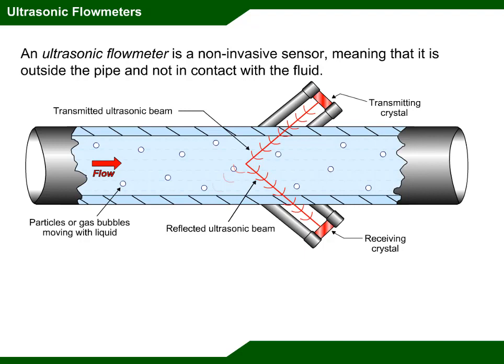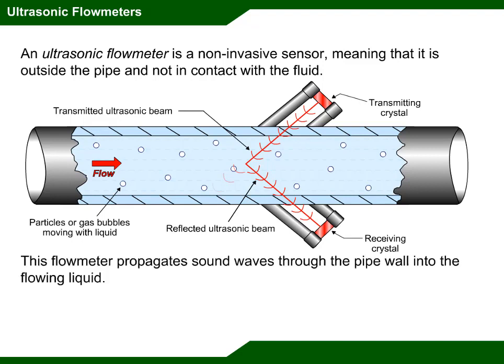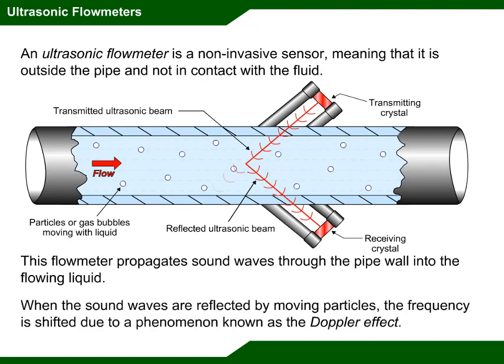An ultrasonic flow meter is a non-invasive sensor, meaning that it is outside the pipe and not in contact with the fluid. This flow meter propagates sound waves through the pipe wall into the flowing liquid. When the sound waves are reflected by moving particles, the frequency is shifted due to a phenomenon known as the Doppler effect.